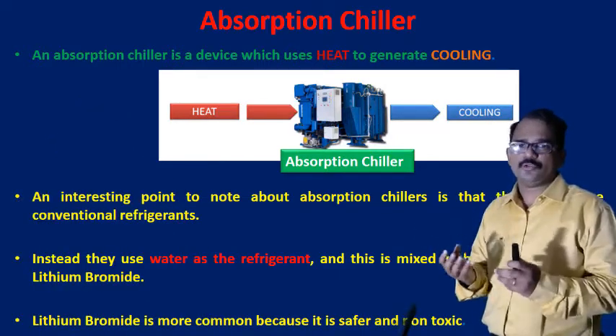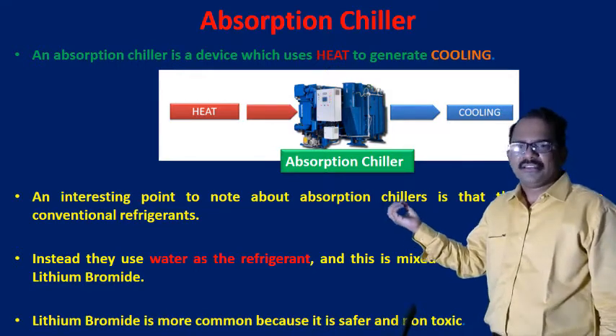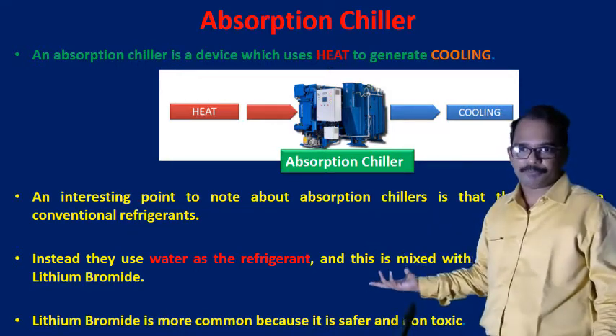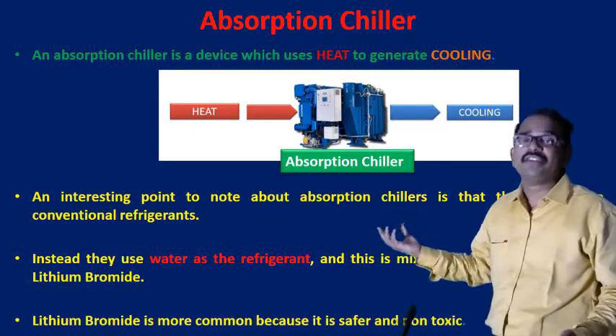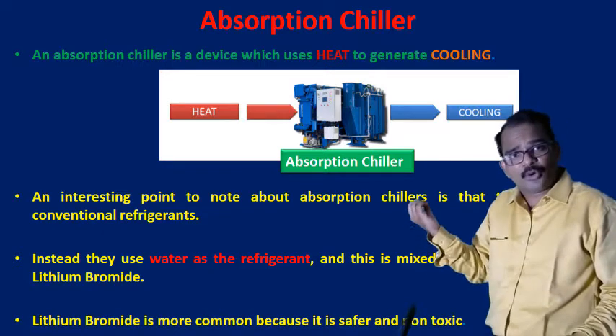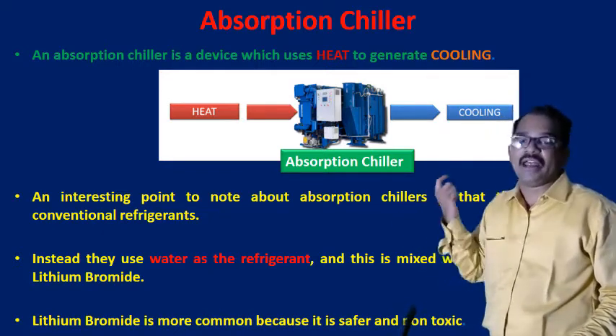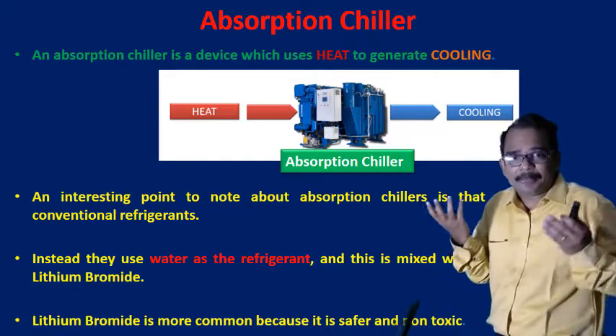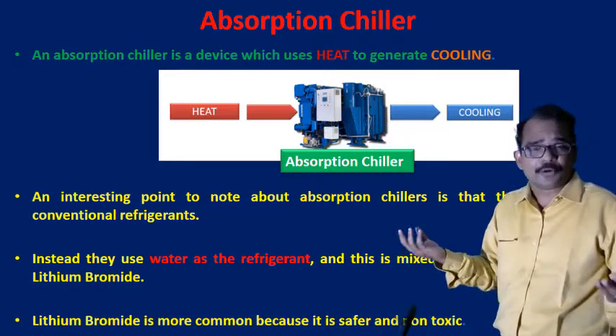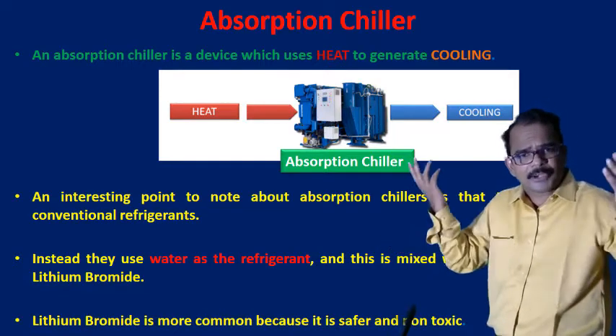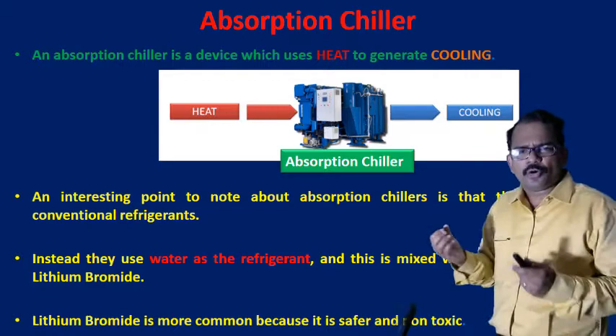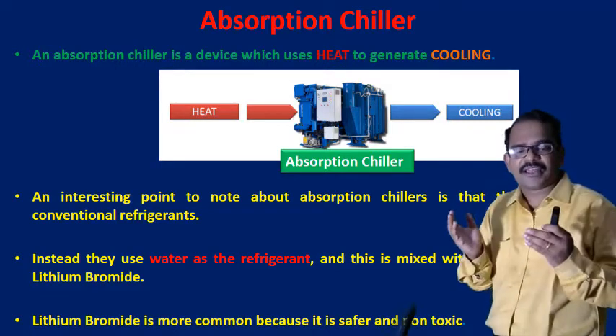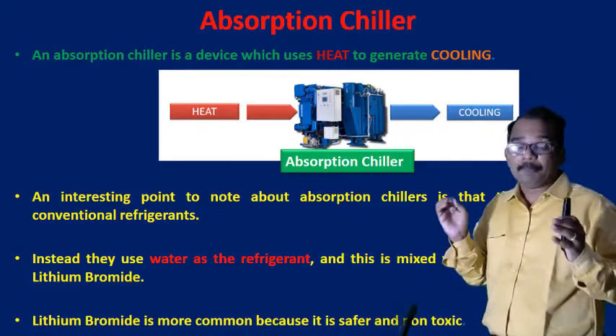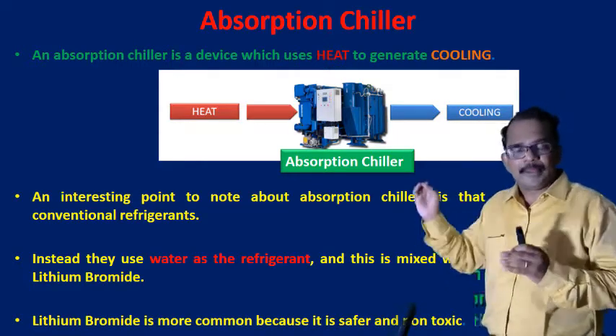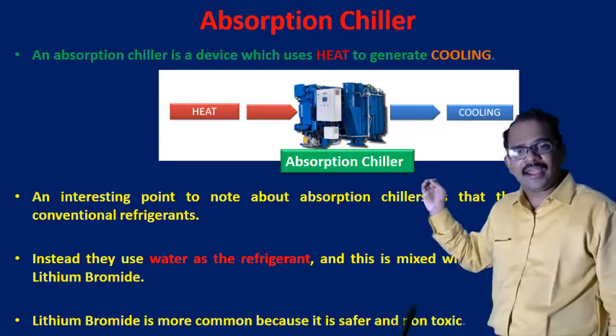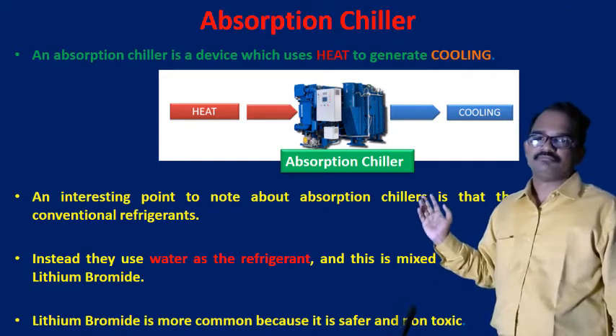An interesting point to note about absorption chillers is that they don't use conventional refrigerants, as already discussed. Instead, they use water as a refrigerant, and this is mixed with either ammonia or lithium bromide. That is why it is an environmentally friendly technology, because it is not producing any CFCs, chlorofluorocarbons, into the atmosphere. Lithium bromide is more commonly used because it is safer and non-toxic when compared to ammonia, and that's why in the absorption chiller we generally use a water and lithium bromide solution.